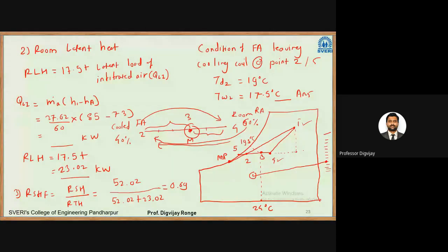I have looked at point A. Then I have calculated their enthalpies. Then I have calculated RSH. Then I have calculated RLH. From that I have calculated the RSHF factor. So this will be my point on that RSHF scale.